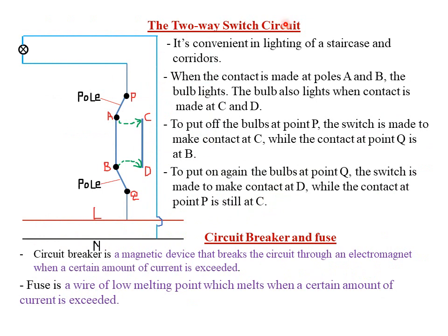Next, we look at the two-way switch circuit, which is convenient for lighting staircases — one switch at the upper end and another at the lower end — or one at each end of a corridor. When pole P is connected to point A and pole Q to point B, the circuit is complete: current flows through the live wire from Q to B to A to P, then through the bulb to the neutral wire, and the bulb lights.